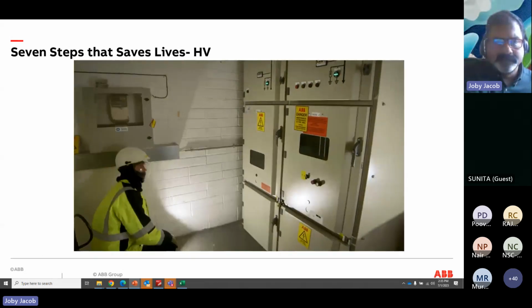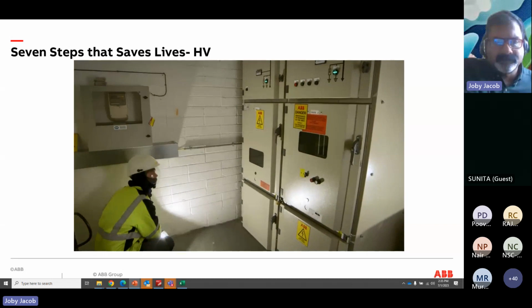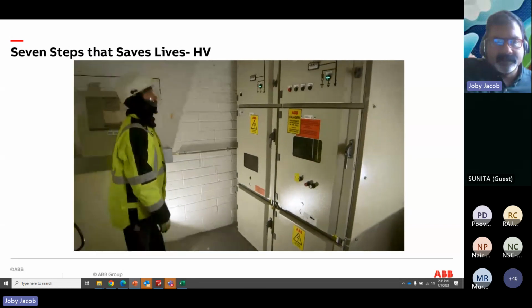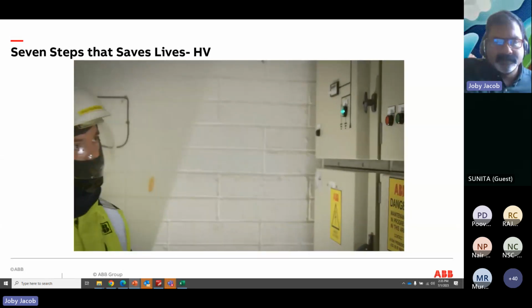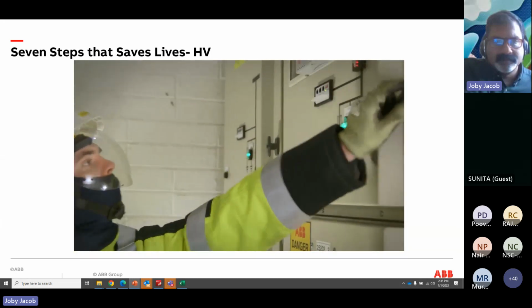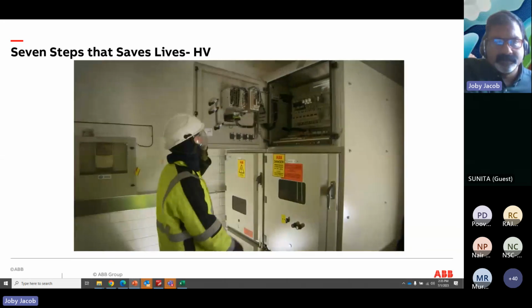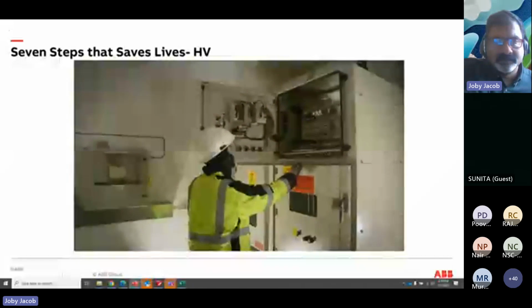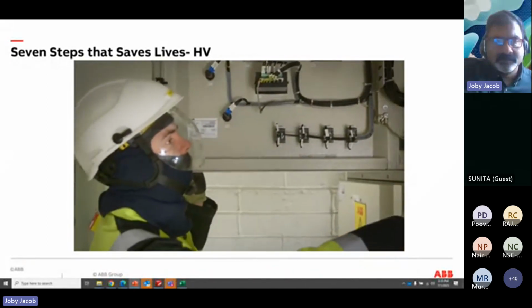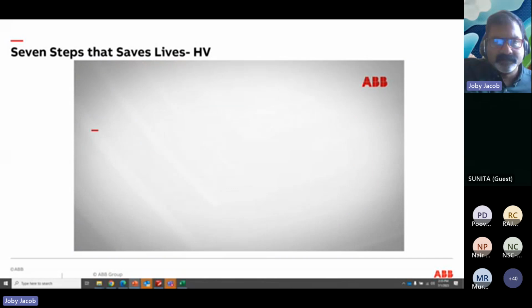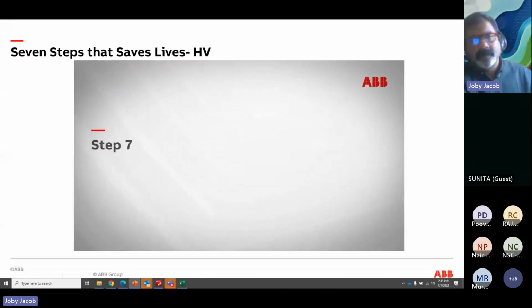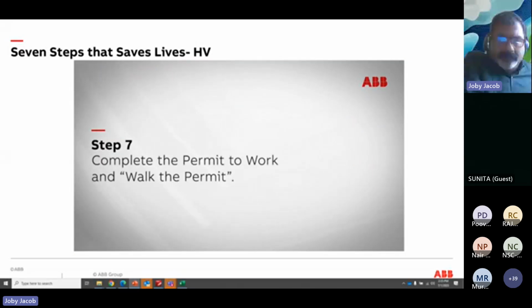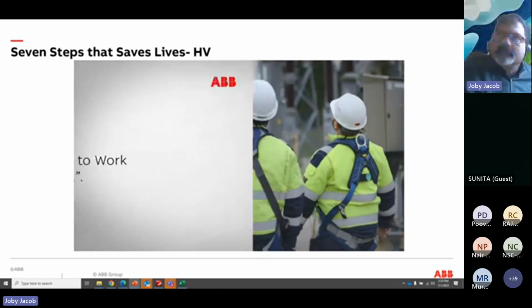In especially dangerous situations, like working closer than 1 meter to the live connections, or where there's low lighting, difficult access, or higher voltages, take extra precautions. Now that you've created a safe work area, you need to take the final step before beginning work, which is Step 7, complete the permit to work and walk the permit.